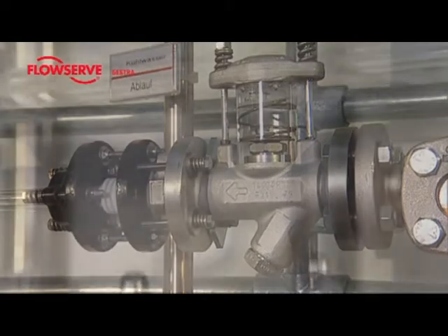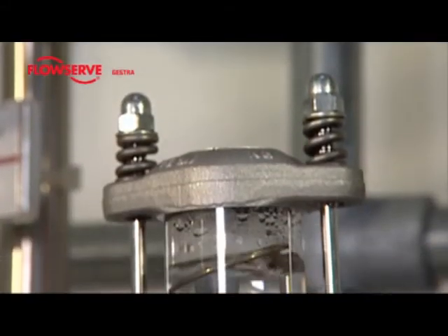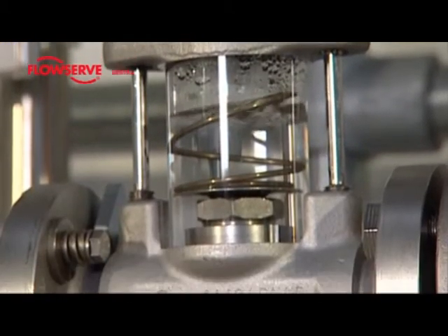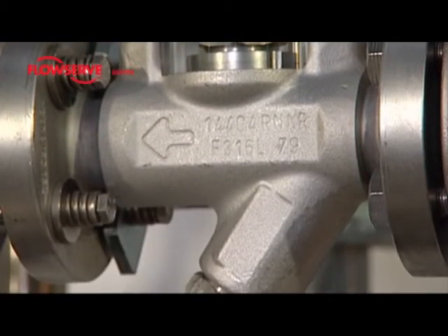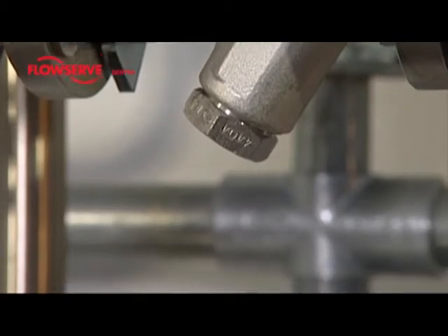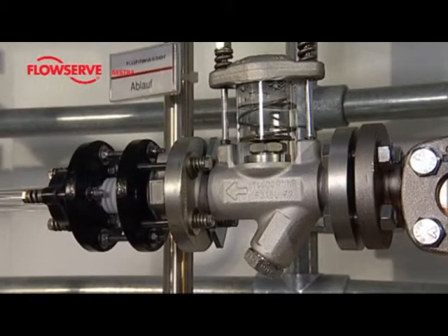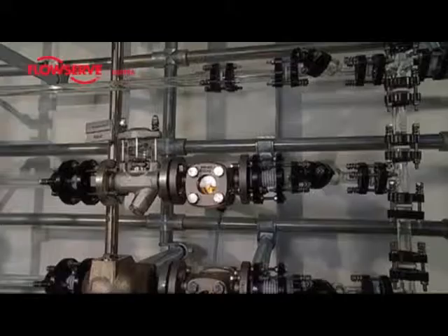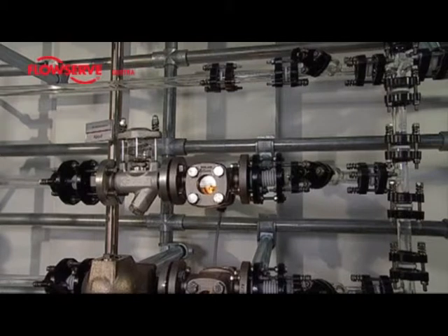Large quantities of condensate are already discharged at low pressure differentials. Even for controlled plants, in which the steam pressure fluctuates, this has hardly any influence on the condensate discharge, which is usually achieved without banking up, provided the steam trap is sized correctly. The back pressure has no influence on the control accuracy.